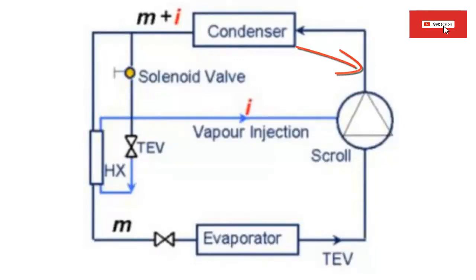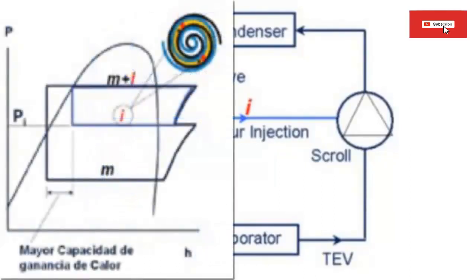20. Reduction of pressure loss in the suction line compared to a conventional system for the same thermal load. 21. A 40% decrease in refrigerant flow through the evaporator can be established. This reduces the pressure drop in the suction line by around 60%.